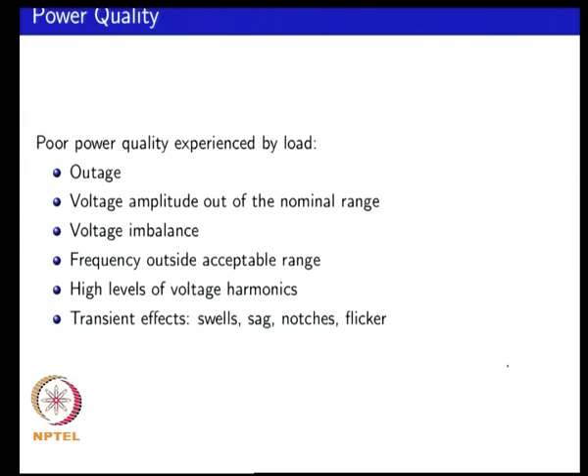The question is what do you mean by poor power quality as seen by the load. A load seeing poor power quality from the supply can be for a variety of reasons. The primary reason being that there is no supply at all — there is an outage and you want to feed your load. If you are having electric supply, you expect your line-to-neutral voltage to be 230 volts. A band of plus 10, minus 20 percent around nominal might be considered acceptable power quality; if you go beyond that you may want to disconnect rapidly.